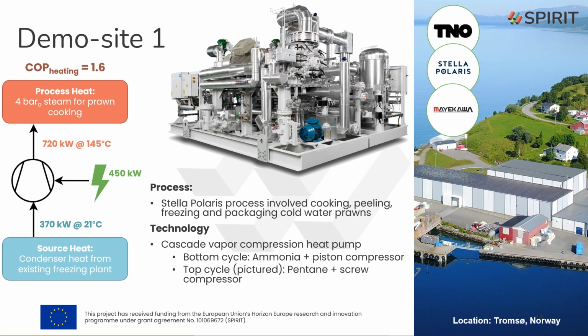We'll use a cascade system to achieve this, with a bottom cycle consisting of a piston compressor and ammonia - technology currently available from Maekawa. The top cycle is really where the innovative part of the process is, producing steam at 145 degrees Celsius using a screw compressor and pentane as the working medium.